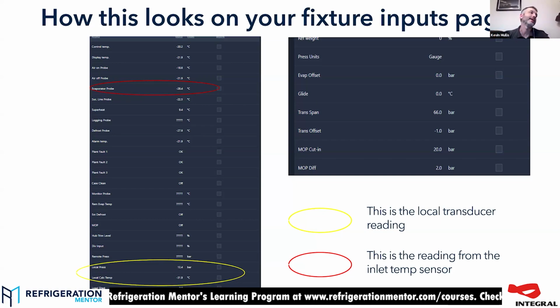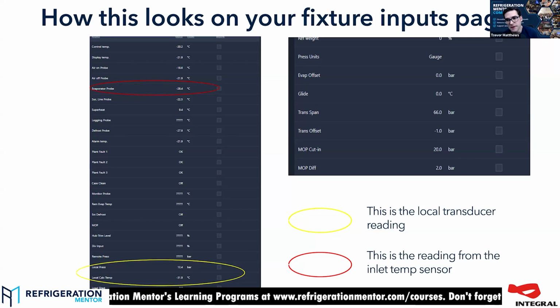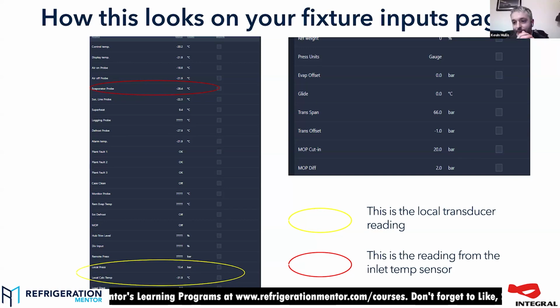The problem with doing it on the first pass? Yeah. But maybe 12 foot away from where the valve is. Yeah. Now that's all fine. That makes perfect sense in terms of you've done whatever expansion you're going to do and you're going to read a proper condition there, but it can hit you with startup. So let's say it's a frozen food case and it's just come off of defrost and the coil's like 10 degrees C. 50, 60 Fahrenheit. Yeah, whatever it works out to be.